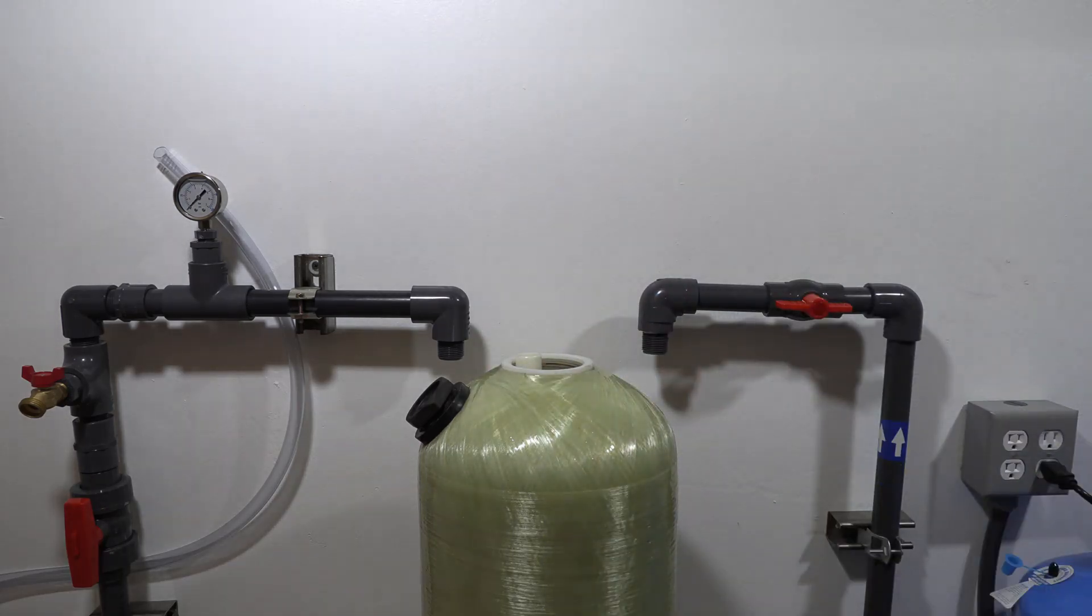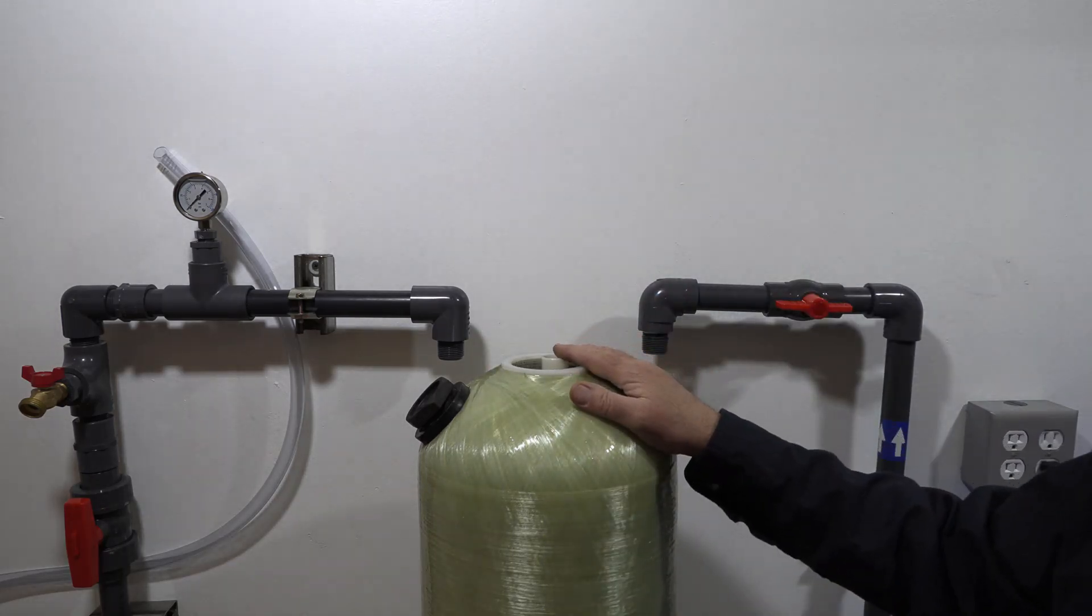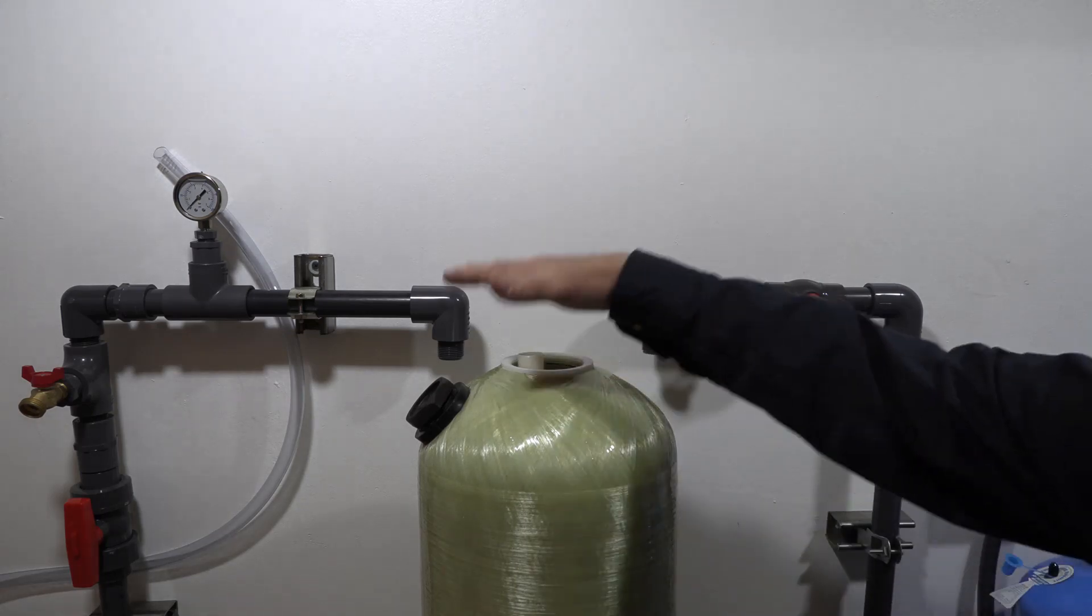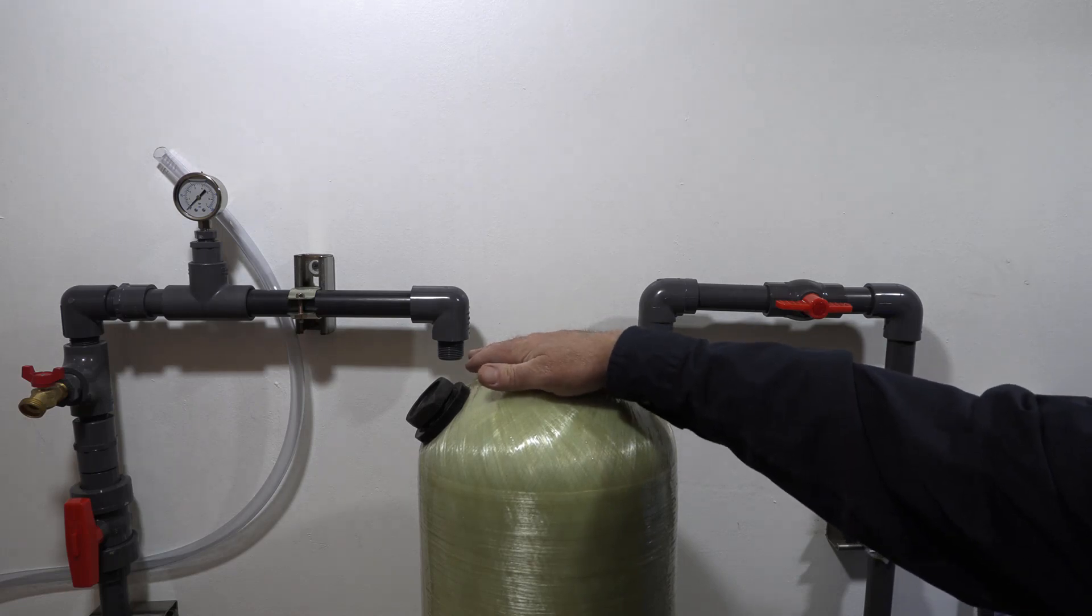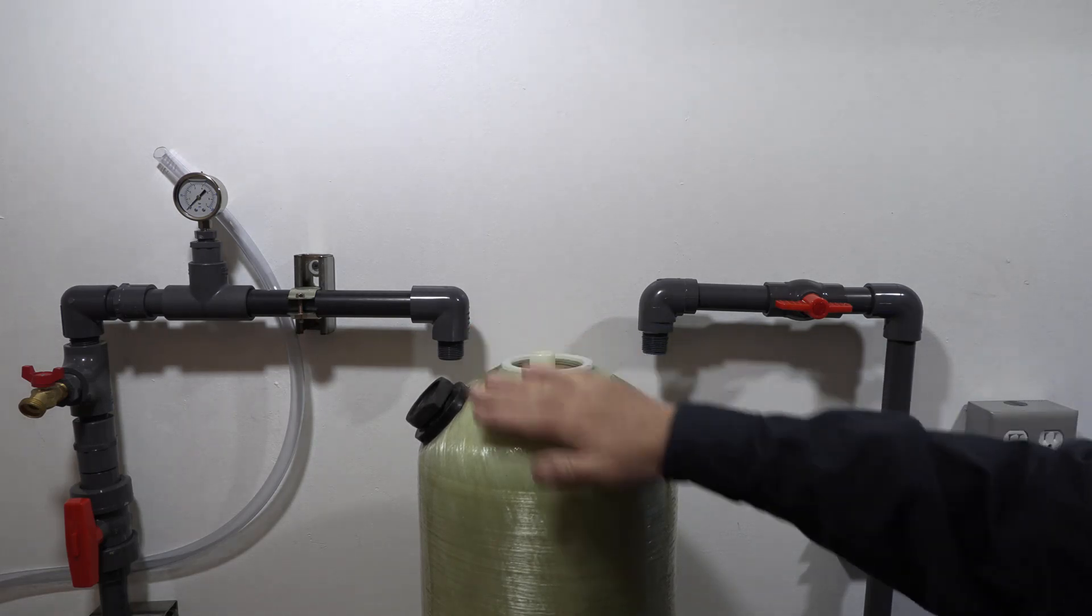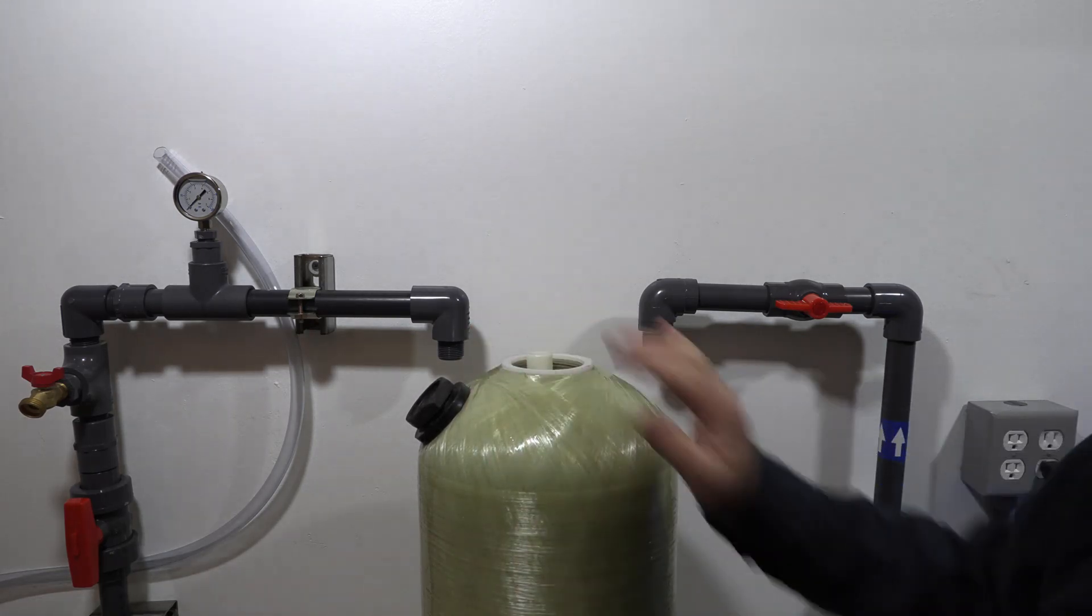Okay, prior to installing our valve, we want to make sure we can fill this up with water. You want to let that set for a minimum of an hour, up to 24 hours. So you want to pre-soak your media prior to installing your valve.